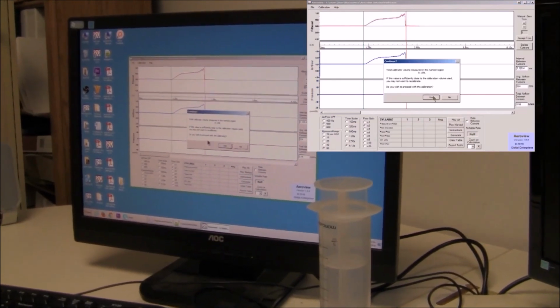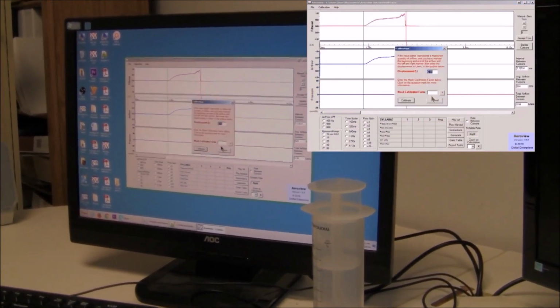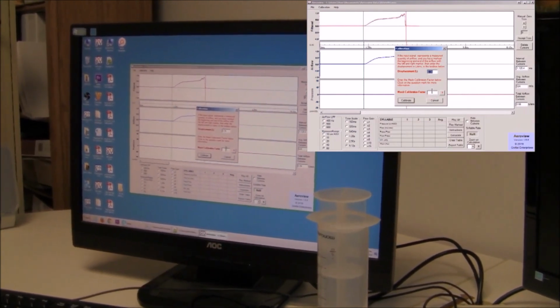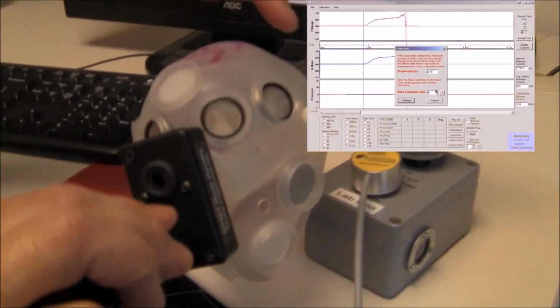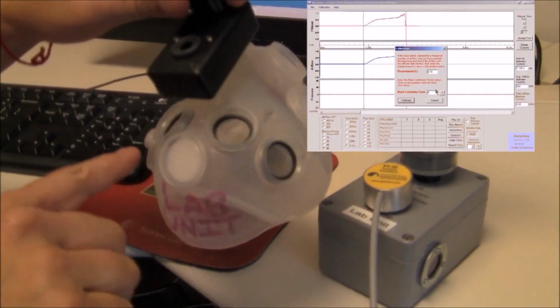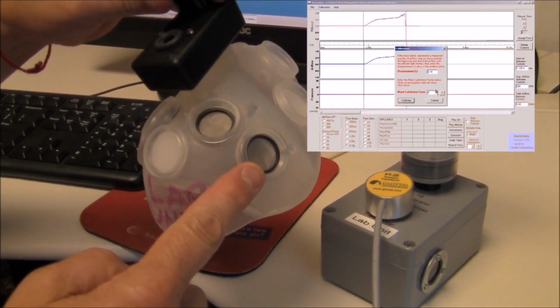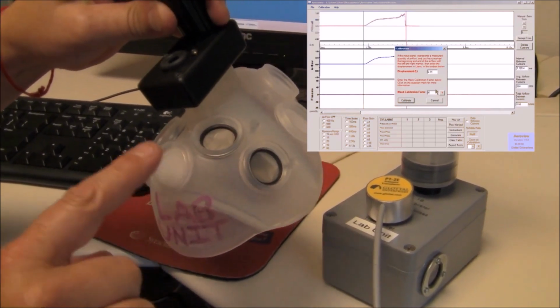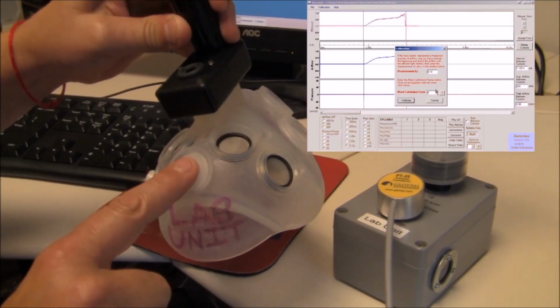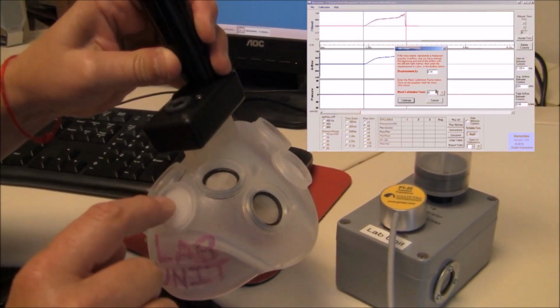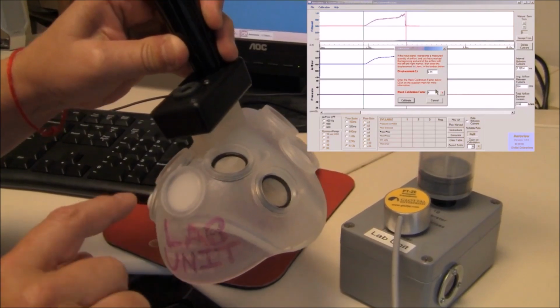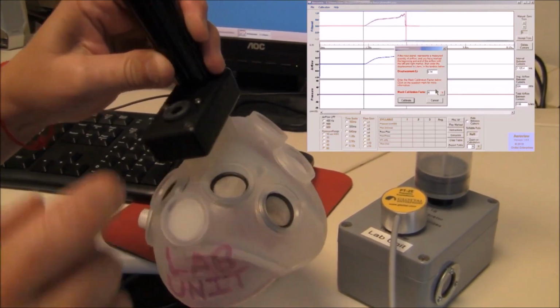So you're going to calibrate airflow, and then you're going to be asked, do you wish to proceed? You pick yes, and then it's 1.4 because of the 140 milliliters, and the calibration factor of 4. The calibration factor relates to how many screen rings you have in your mask. Right now we're using 4 screen rings, so we pick a calibration factor of 4. If you're using the 5th screen ring, then you would pick 5. But we ship the mask with this not being used, so you're going to pick 4 as your calibration factor.